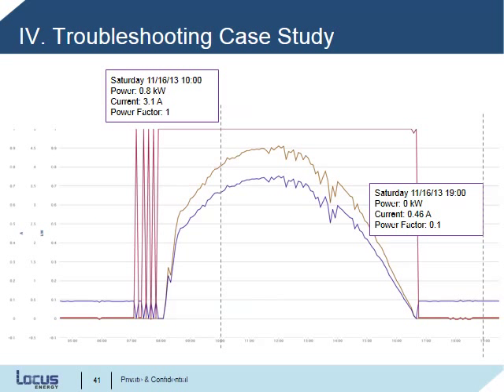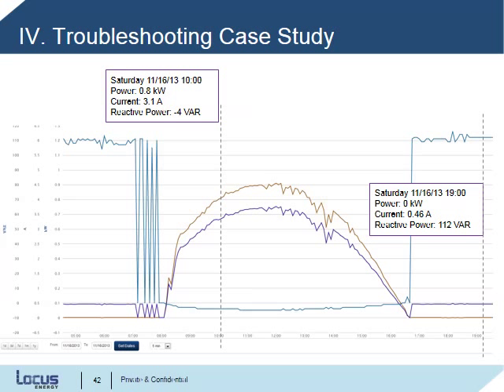Before sending someone on site, we took a look at the data in the charting tool and found that power factor, which is the ratio of real power to apparent power, hovered right around 1 for most of the solar day, so it was a pretty efficient system. At night, this dropped to 0, so nothing unusual there. In this chart, you can see power factor graphed in red. Next, we graphed reactive power against current and real power. In this chart, you can see reactive power in blue.